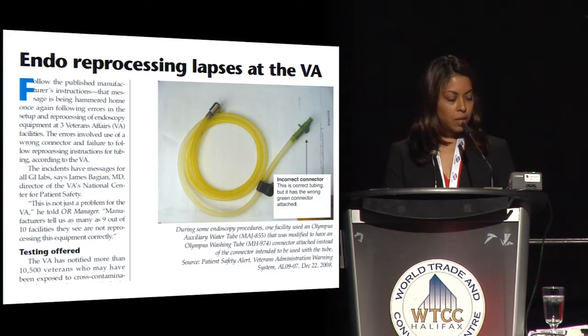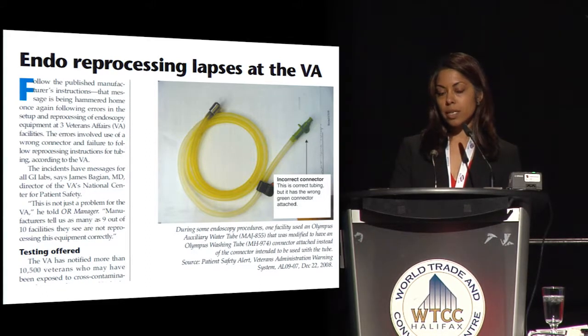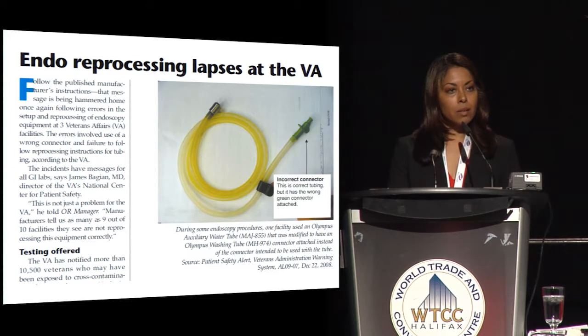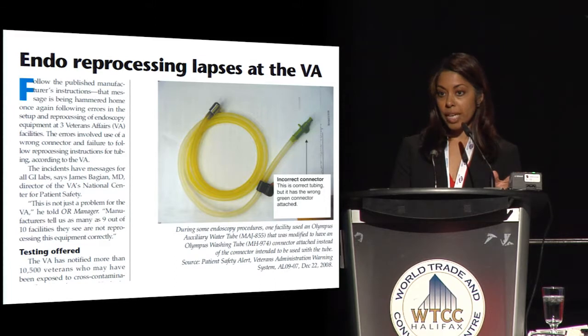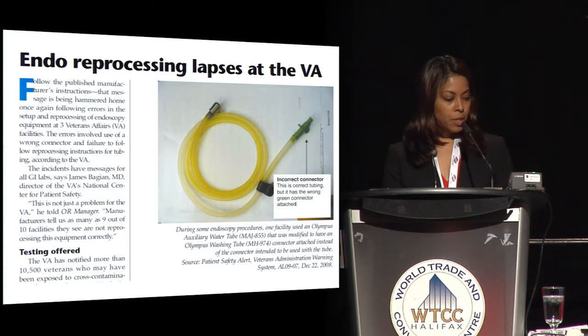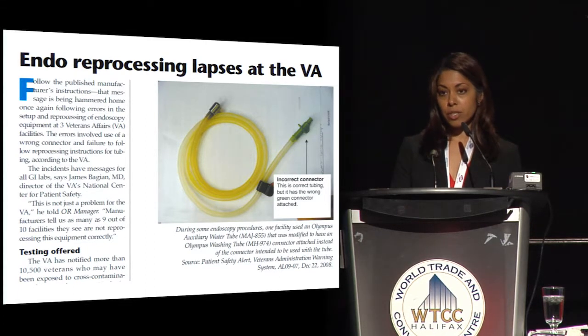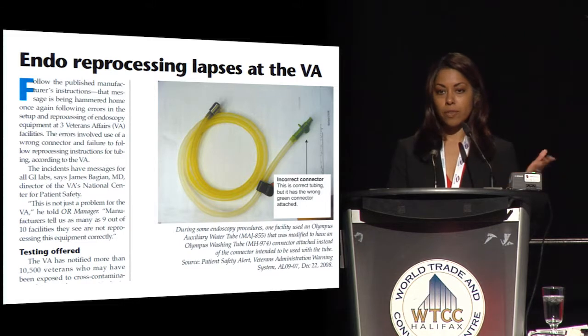So the first case here was published in 2009, and this involved a number of breaches in the reprocessing of endoscopes in 3 Veteran Affairs hospitals throughout the United States. Basically, the errors came down to 2 areas that were being improperly dealt with. One was that a lot of the auxiliary water channels used for irrigation had the improper connectors attached to them. This picture is up here specifically for people to be aware that this wrong connector looks very, very similar to the one that should be there. But this particular one did not have a one-way valve. So the resulting problem is you could get backflow through the irrigation process of bodily fluids into the instrument.